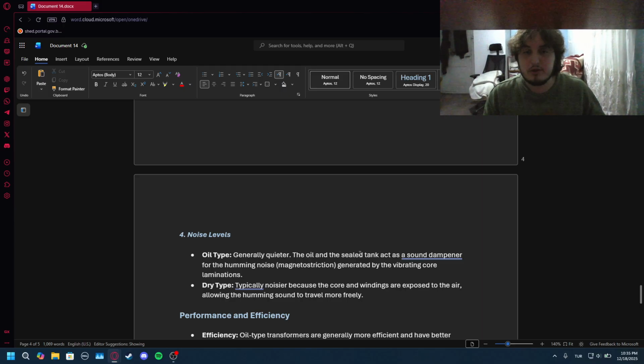Noise levels. Oil type, generally quieter. The oil and the sealed tank act as a sound dampener, and it makes it really, really quiet. For the humming noise, magnetostriction, generated by the vibrating core and laminations. Dry type, typically noisier because the core and the windings are exposed to air, allowing the humming sound to travel more freely.